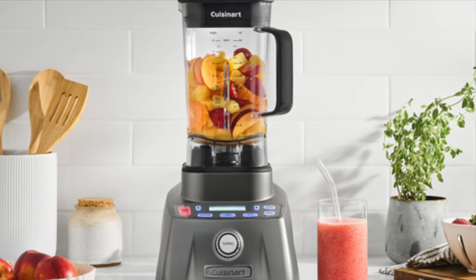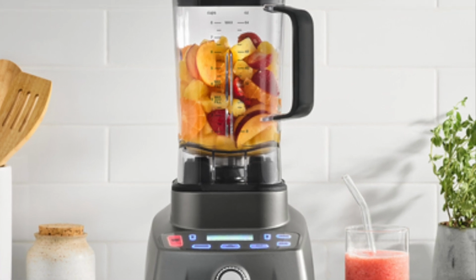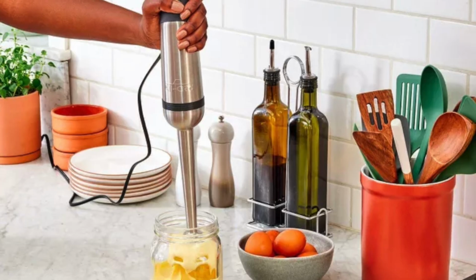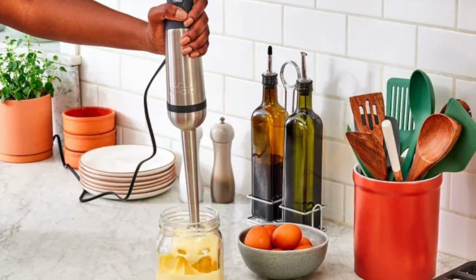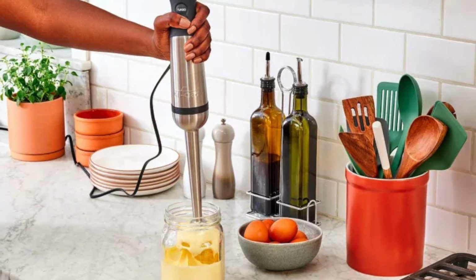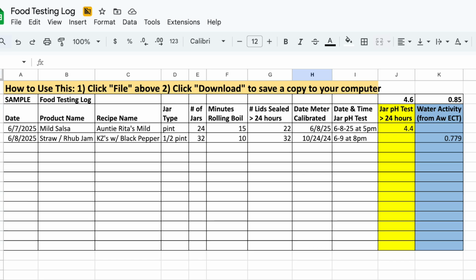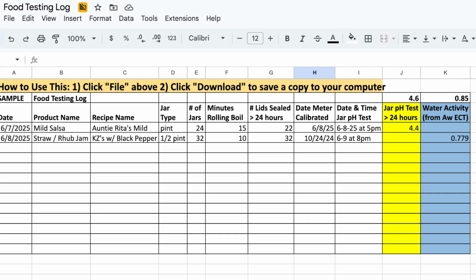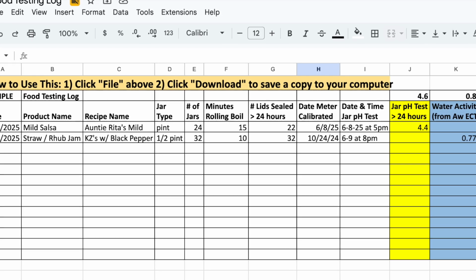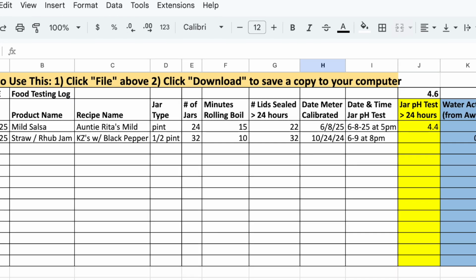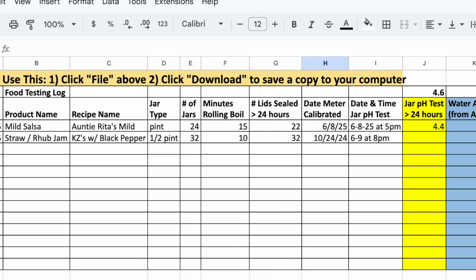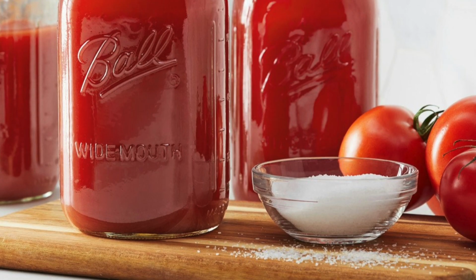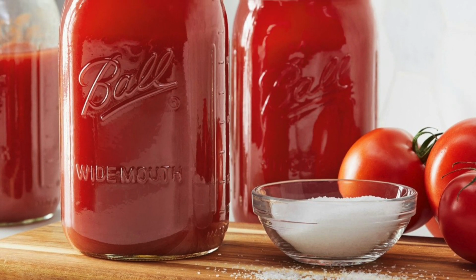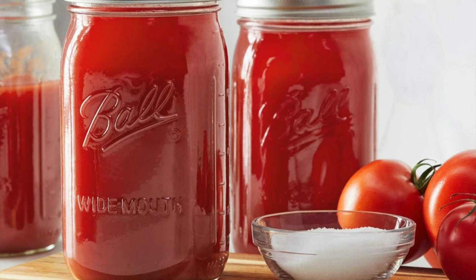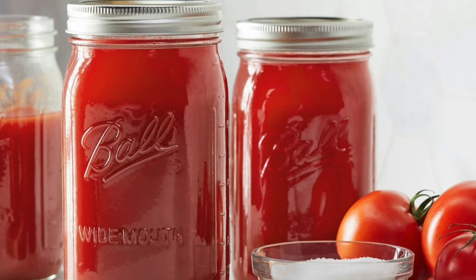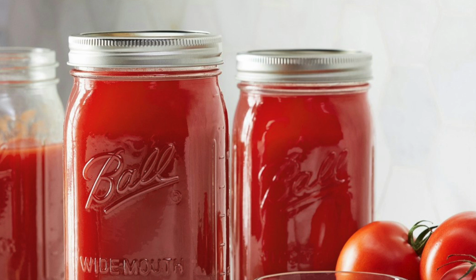Using a blender or an immersion wand, blend the solids into a consistent slurry. If needed, you can add a small amount of distilled water to produce the slurry. Test the slurry mixture and write down the value. Step 4, the pH value from the liquid and the slurry must be 4.6 or below. For canned foods, you will need to test after the food is canned. The lid has sealed and the food has cooled, but within 24 hours of canning.